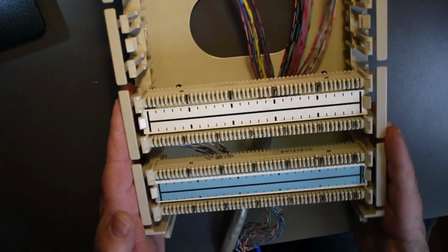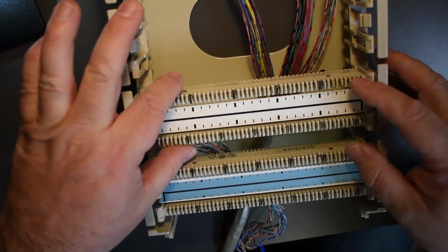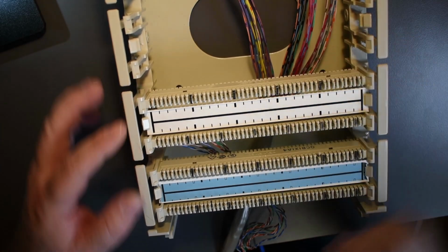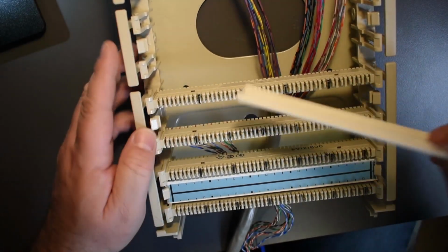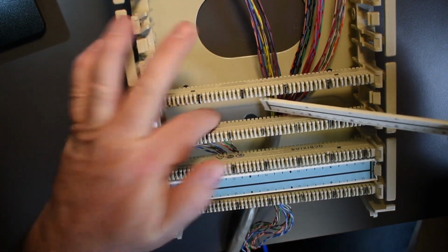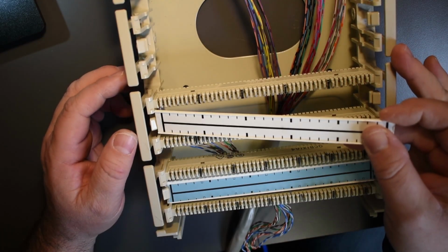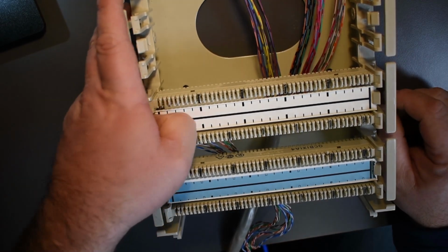So that's how these things work. The idea is, on the outside of the pair of the strips, the wire is not there. Right? All the wire should be hidden within the pair here. So this is where the wire should be terminated, and all these loose ends or slack can be covered with the termination or designation strip.